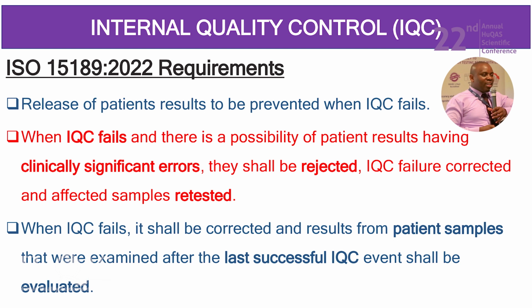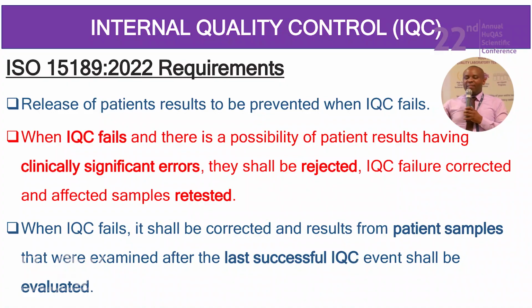Now you get this. I don't know whether it has sunk. You ran the IQC yesterday. It passed. Very good. And you proceeded with patient analysis. Then today, you run your IQC, it fails. You're being told, when IQC fails, it shall be corrected and results from patient samples that were examined after the last successful IQC event shall be evaluated.